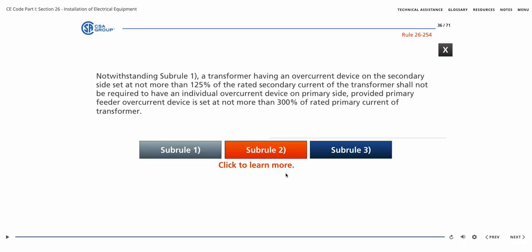Subrule 2. Notwithstanding Subrule 1, a transformer having an overcurrent device on the secondary side set at not more than 125% of the rated secondary current of the transformer shall not be required to have an individual overcurrent device on the primary side, provided the primary feeder overcurrent device is set at not more than 300% of rated primary current of the transformer.